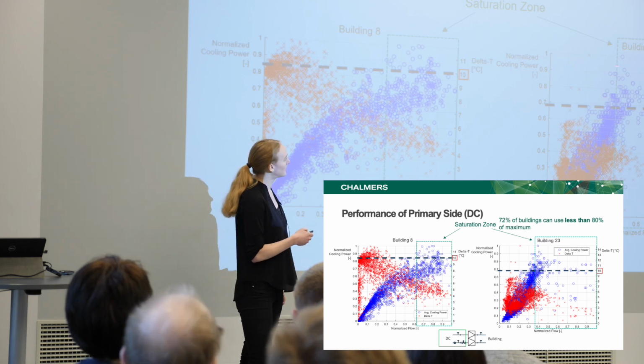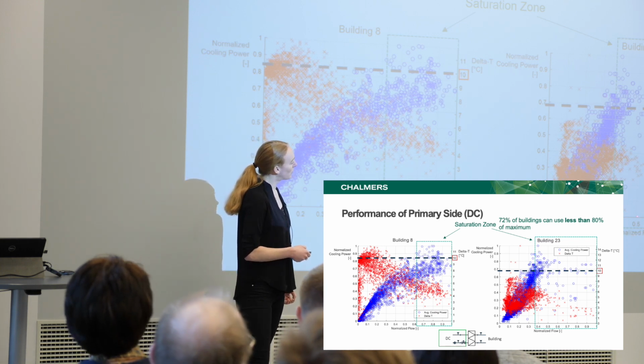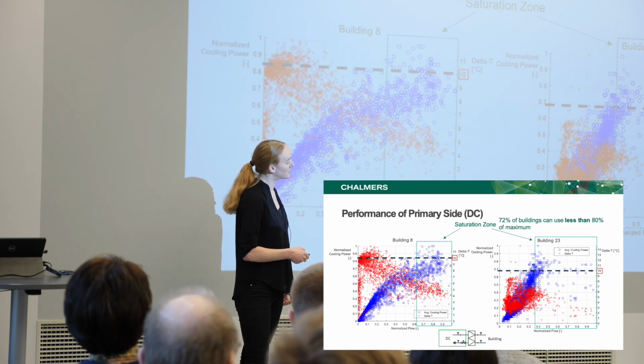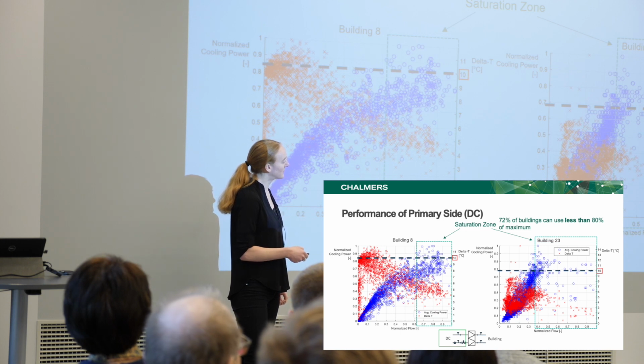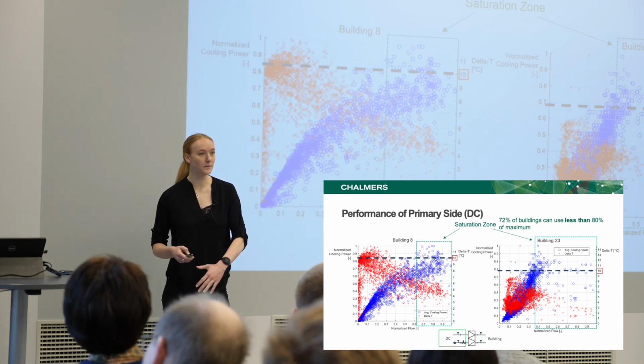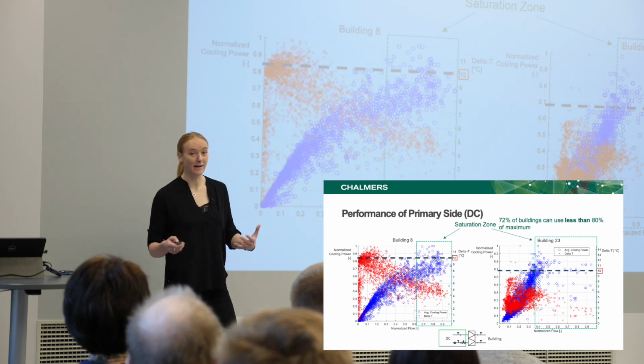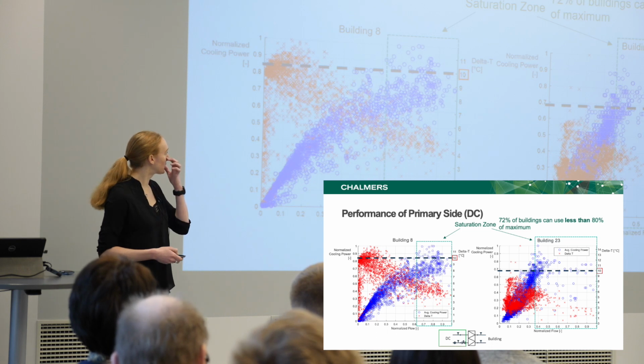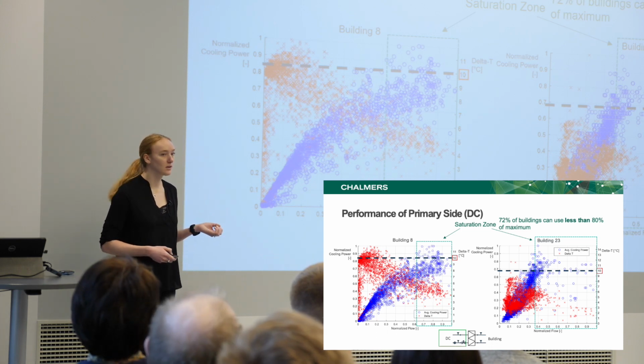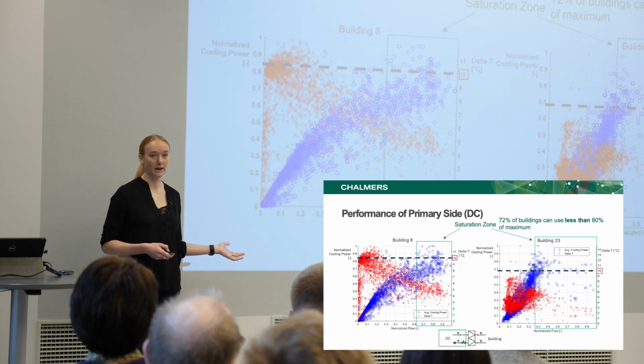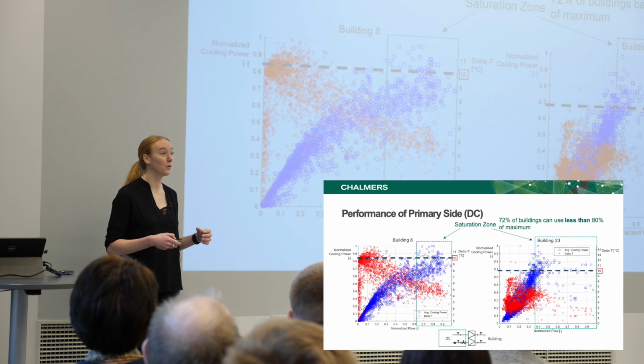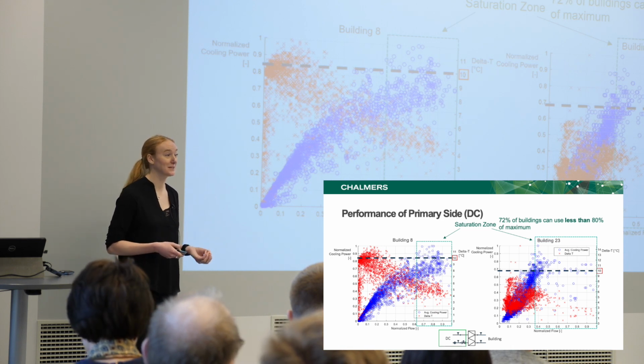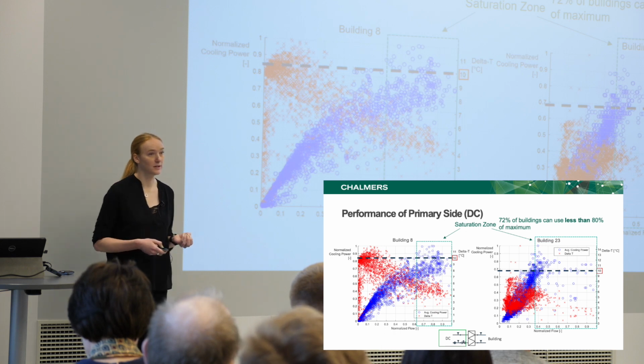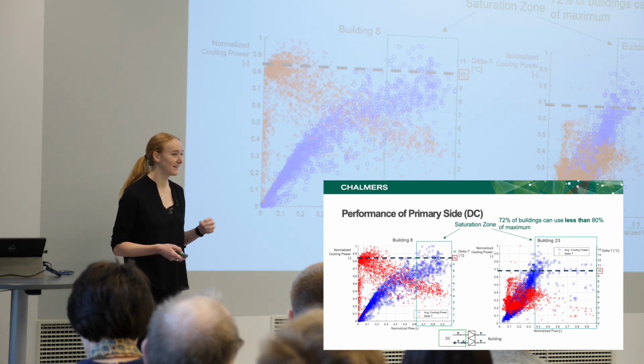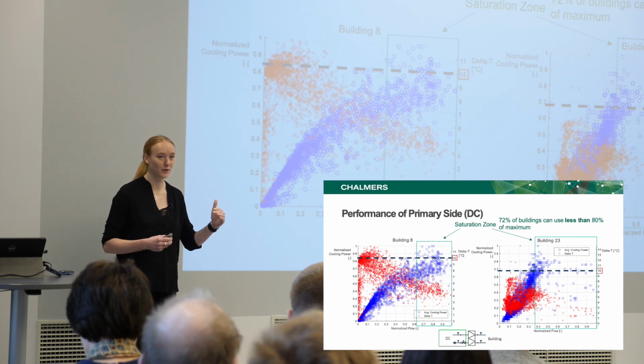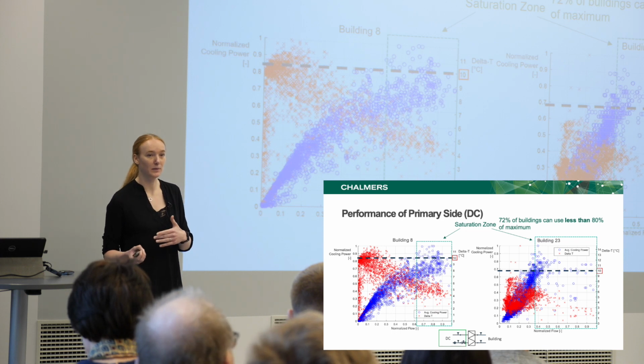And the same for this one. Here is maximum cooling power for a flow around 40% of the used maximum. Everything else besides this just causes delta T to drop, and you don't get more cooling power for a higher flow. So it was actually observed that 72% of the buildings can use 80% or less of their maximum flow rate, where maximum means the flow rate that has been measured during the cooling season of 2018. So most buildings actually use too high of a flow rate, and that is connected to what I talked about before, how much the control valve opens depending on the settings of the supply temperature set point in the buildings.